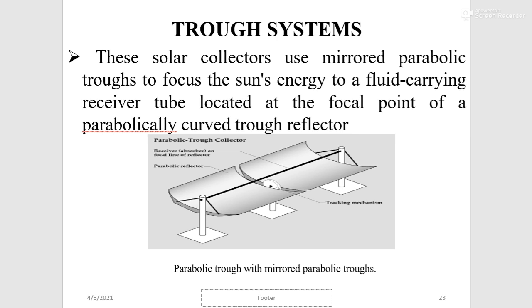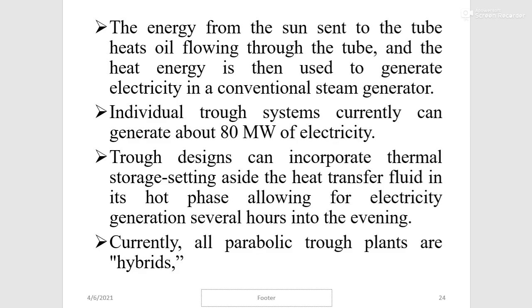Trough systems use mirrored parabolic troughs to focus the sun's energy onto a fluid-carrying receiver tube located at the focal point of a parabolically curved trough reflector. The energy from the sun heats oil flowing through the tube, and that heat energy is then used to generate electricity in a conventional steam generator. Individual trough systems can currently generate about 80 megawatts of electricity. Trough designs can incorporate thermal storage — setting aside the heat transfer fluid in its hot phase — allowing for electricity generation several hours into the evening.